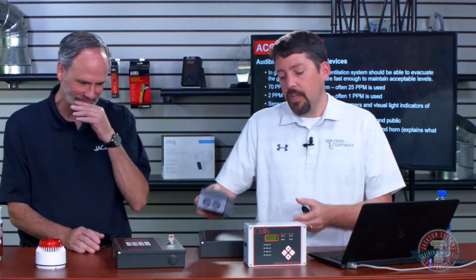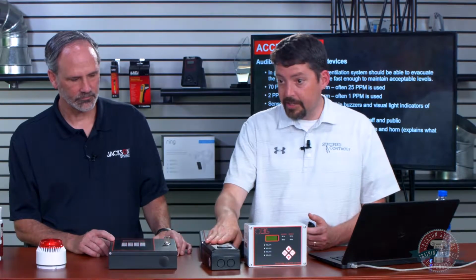That one's about 120. So what I'm getting at is everybody out there that makes this is going to meet that spec. But what they're not going to provide in their product is a strobe and horn. An actual light that they can see, an actual horn that they can definitively hear that is specifically for this purpose. Also, I'll point out that with gas detection, OSHA's requirements are that it is a constant buzzer. So, smoke alarms are that bing, bing, bing. This is supposed to be a constant buzzer sound. This is a constant buzzer, but it's not nearly what the engineer probably thinks it is.